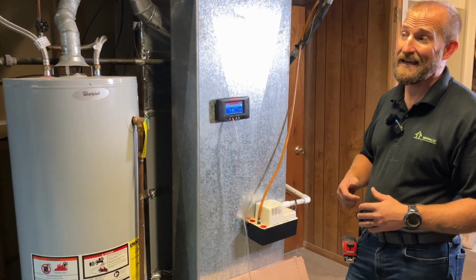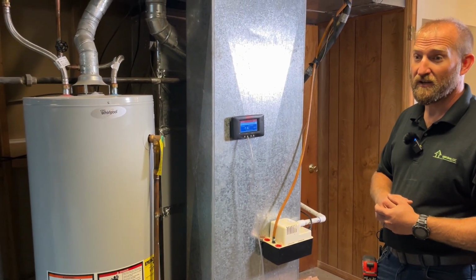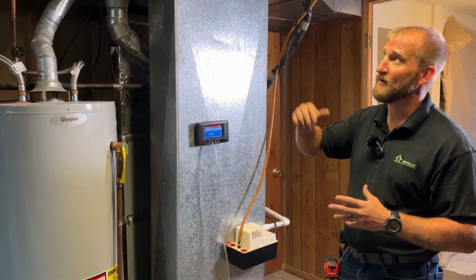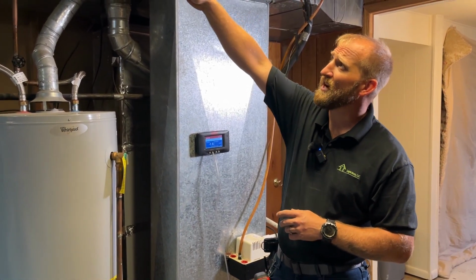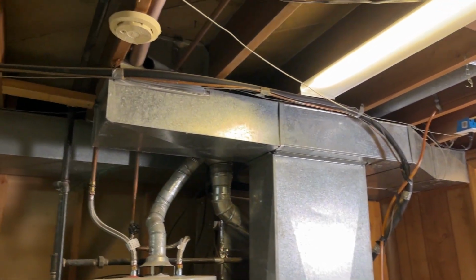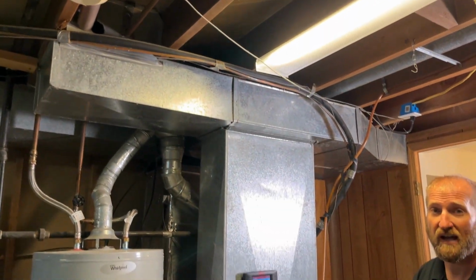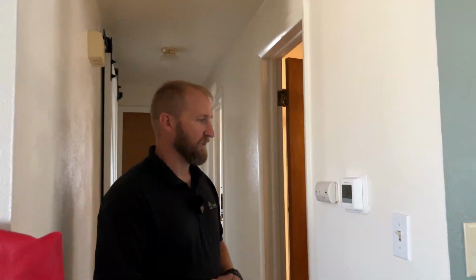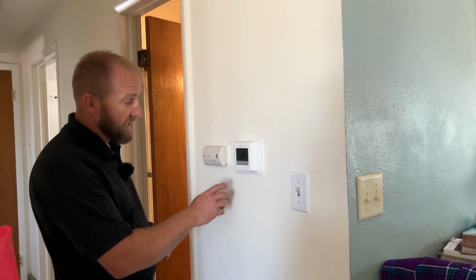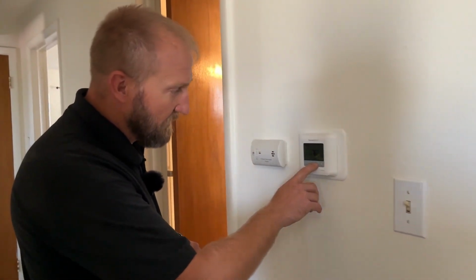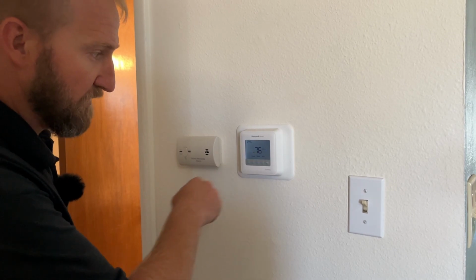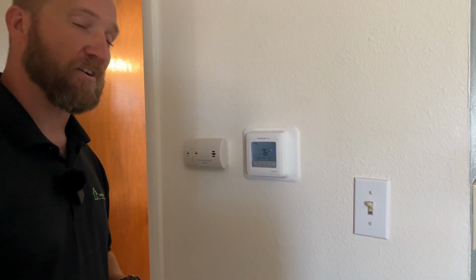So now we're going to turn the fan itself on for the furnace to see how leaky the returns are down here. We can already see that there's some holes in the pan returns here. So that's going to probably depressurize the CAZ a little bit more for us with that fan on. Up here at the thermostat, everyone's going to be a little different. Sometimes you have to go through the settings to find your fan. This one's pretty easy. Go to fan on. It should be kicking our fan on down in the CAZ.